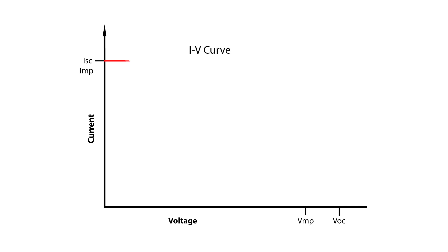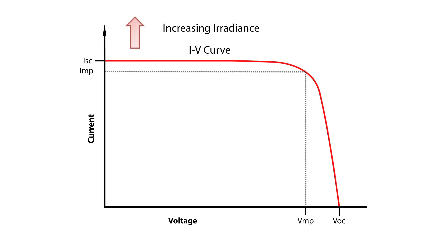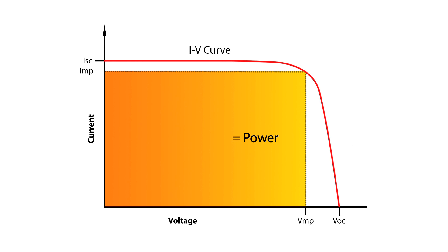The IV curve of a string of PV modules represents all the current and voltage values at which the string could be operated, or loaded, at the existing irradiance and temperature conditions. The IV curve for a properly operating string is shown here. The height of the plateau varies with irradiance. The open circuit voltage, where current drops to zero, varies with cell temperature. Power is the product of current and voltage, thus maximum power is achieved at the knee of the IV curve.